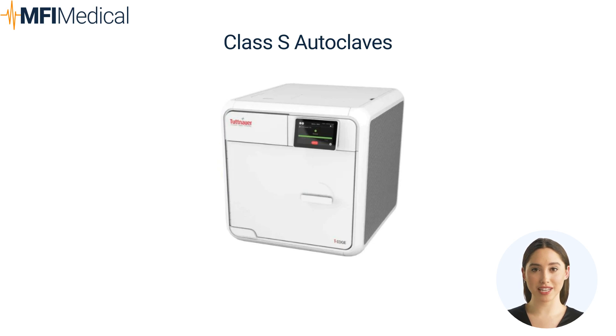Example: Tuttnauer T-Edge 10 or Tuttnauer T-Edge 11 autoclave. The T-Edge 11 is available in both a Class B and Class S model, each with unique features. The Class B model includes a virus protection shield cycle that heats trays up to 180 degrees for 15 minutes, eliminating bacteria, viruses, and fungi including coronavirus, using a pre/post-vacuum method. The Class S model uses gravity steam sterilization, and customers can upgrade from Class S to Class B via a USB software update.